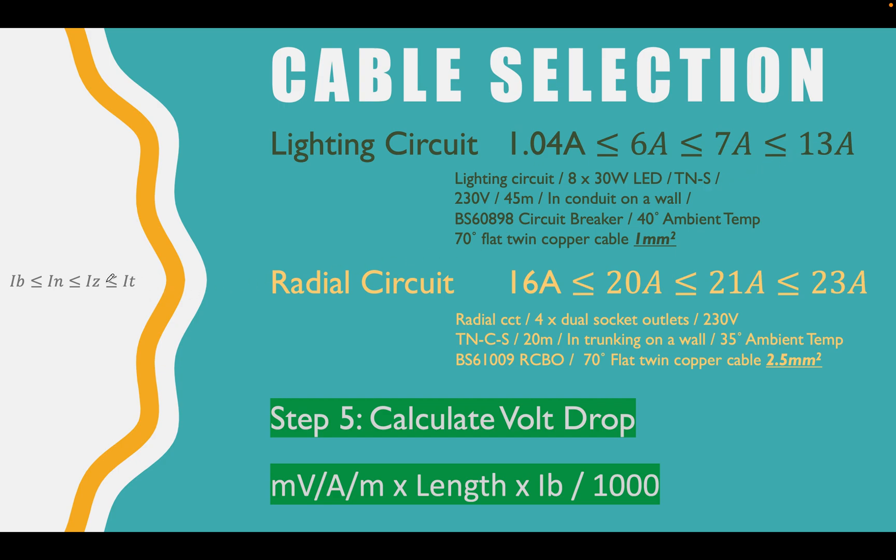Look over here, IT has to be greater or equal to IZ. IZ was the current carrying capacity of the cable in the conditions it's going to be in, 7 amps. And IT is the tabulated value for this actual cable that we choose, which is 13 amps. So we're happy with those selections on each side.